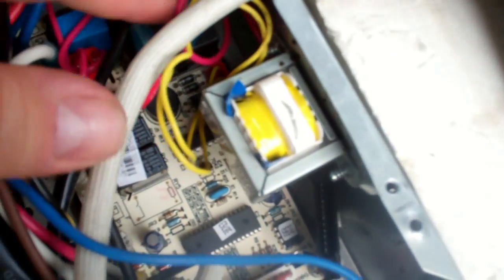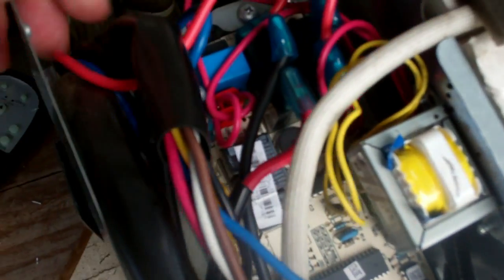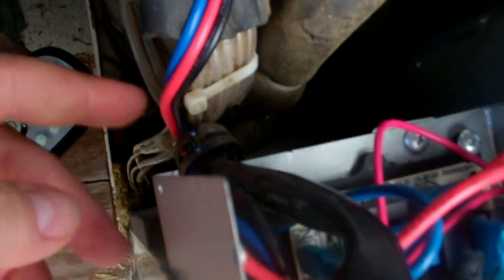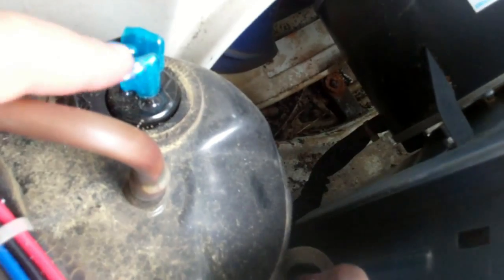So RY7, which is this one right here, there's the connection from here to P11. You can see P11 on the board right there. The other wire, which is this long one, goes all the way down here and follows right into the top of the compressor itself.